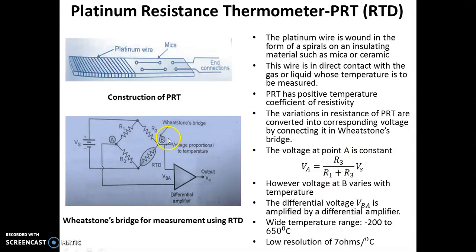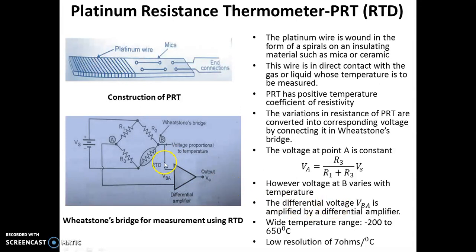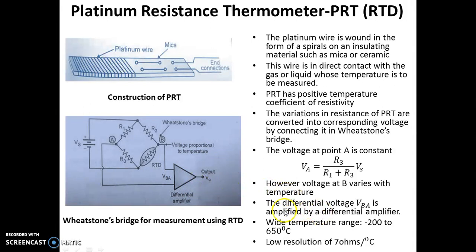However, the voltage at point B is proportional to temperature. The voltage VBA is a differential voltage which is the output of the PRT. This output voltage is amplified by using a differential amplifier. PRT has a wide temperature range — from minus 200 degree Celsius to 650 degree Celsius. But PRT has low resolution; for each degree Celsius change in temperature, the resistance of PRT changes by only 7 ohms, which is one of the limitations of PRT.